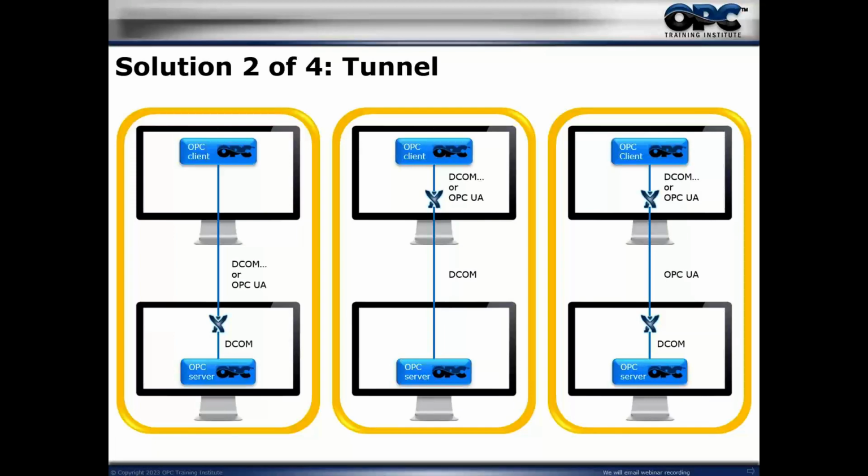Klaus, can I simply uninstall the patch if we have a problem? Yeah, you can uninstall the patch. Will, you're asking, will this update affect OPC UA as well as DCOM? So this patch affects only DCOM. OPC UA does not use DCOM, therefore OPC UA is not affected by this. Keep in mind, underneath the hood, your OPC UA might be connecting to some DCOM, so it might be affected, but OPC UA itself is not affected. This is only affecting DCOM installations.